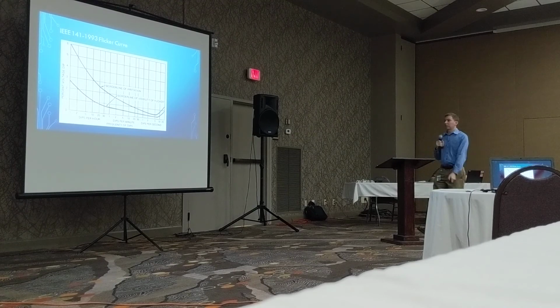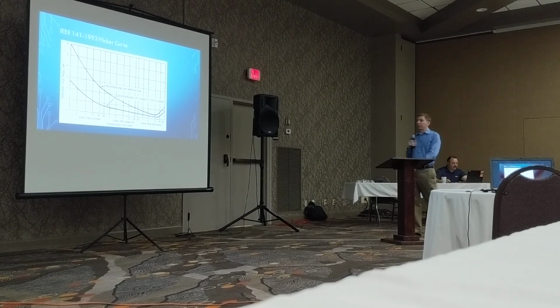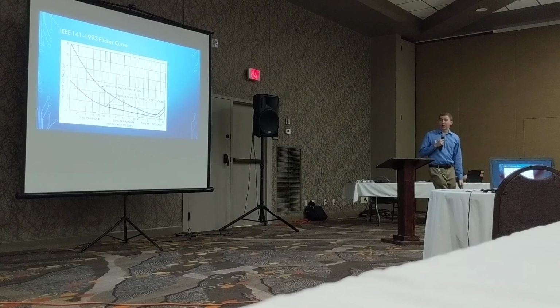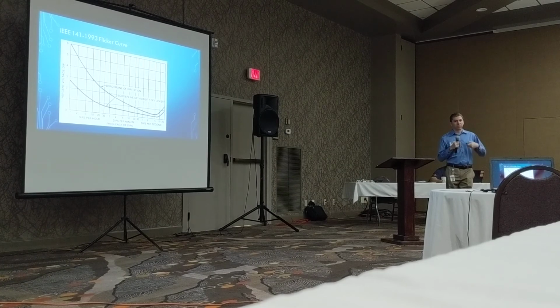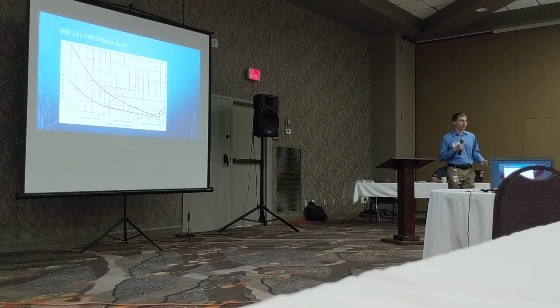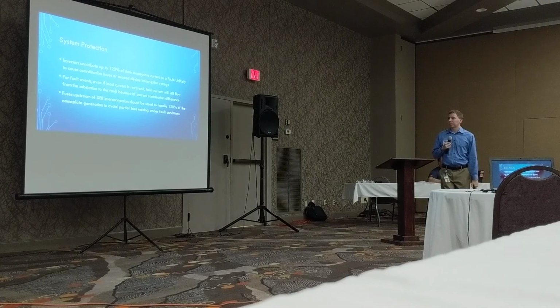So here's our flicker curve. You can see at the bottom is dips per hour. The left side is what percentages. And then you've got the borderline of visibility and the irritation. At 20 dips per hour, it's at about 2.5%. So that's the criteria that we use. Anything over 2%, we kind of start looking at and determining whether it's okay based on what types of customers are on there, what types of loads, past history, those types of things. So that's our flicker process.